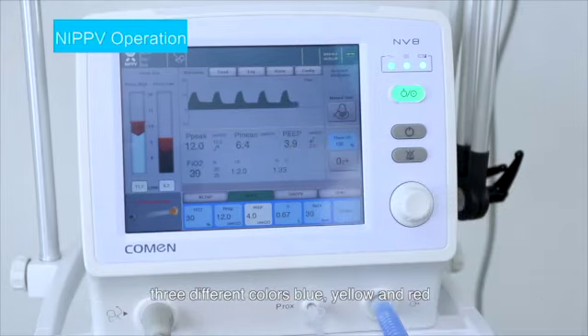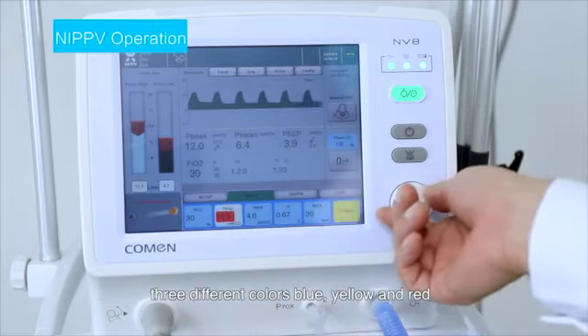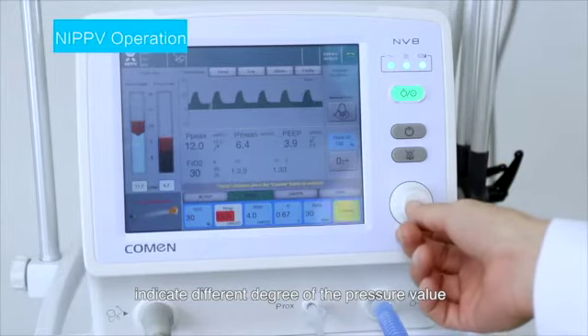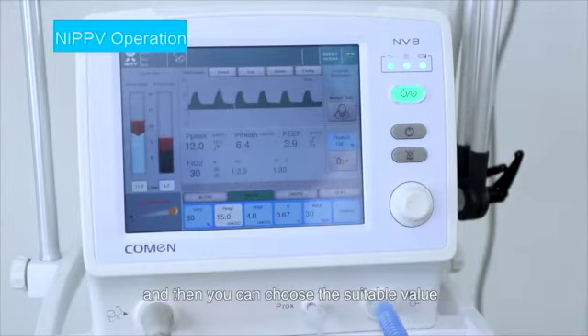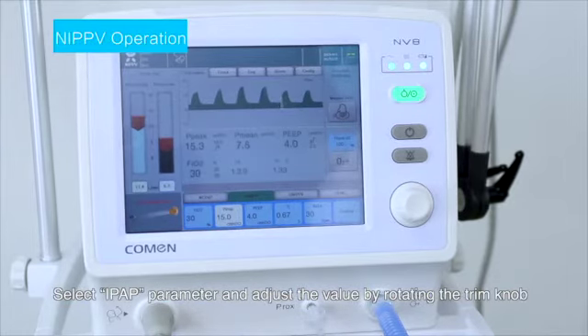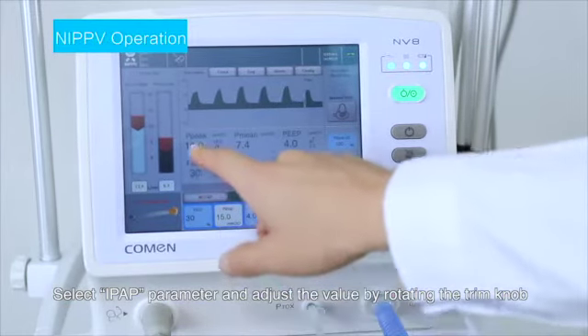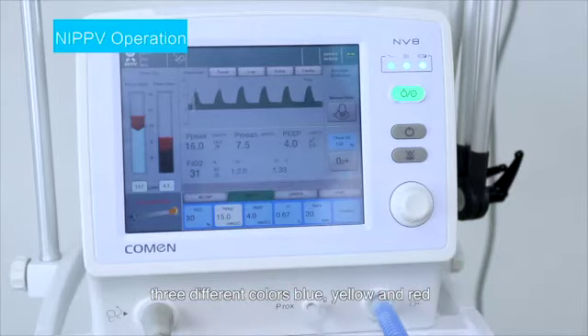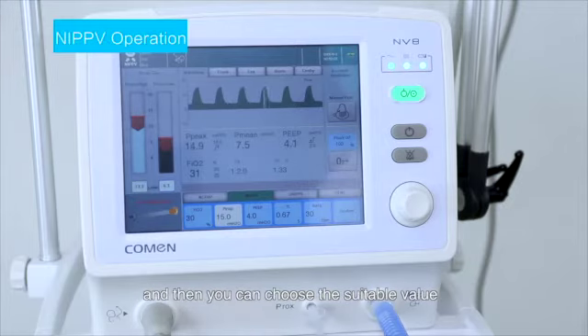3 different colors, blue, yellow, and red, indicate different degree of pressure value, and then you can choose the suitable value. Select IPAP parameter and adjust the value by rotating the trim knob. 3 different colors, blue, yellow, and red, indicate different degree of pressure value, and then you can choose the suitable value.